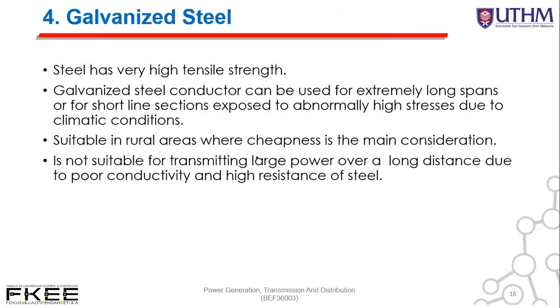Galvanized steel has very high tensile strength. Galvanized steel conductors can be used for extremely long spans, or for short line sections exposed to abnormally high stresses due to climatic conditions. They are also suitable in rural areas where cheapness is the main consideration, as steel is cheaper than aluminium and copper. However, it is not suitable for transmitting large power over long distances due to poor conductivity and high resistance.